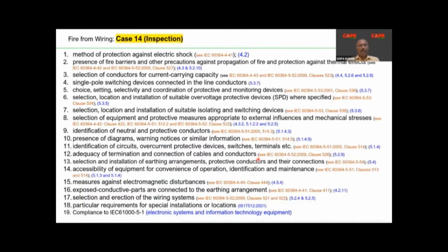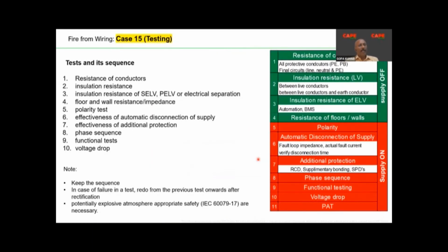Then case 14, inspection. It's quite unfortunate that even though the IS standards and codes include inspection and testing in a very detailed way, the number of engineers or installations where this is followed is quite less. For example, there are about 18 or 19 points to be inspected by a person for the purpose of safety, and there are about 10 different items which we are supposed to test, like resistance of conductors. You see the number 6, effectiveness of automatic disconnection of supply, just to ensure that your MCBs are operating or not. MCBs are installed for the purpose of providing safety, and if they are not tripping, you are in trouble. So there are associated tests. We are supposed to do the test.